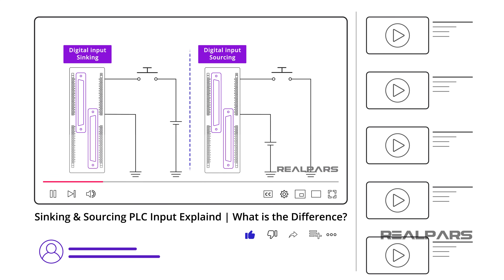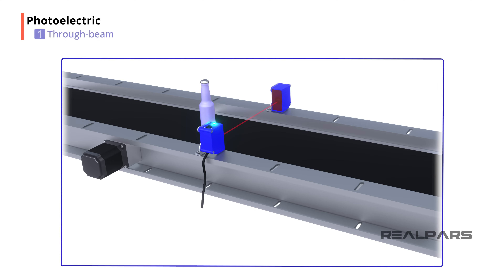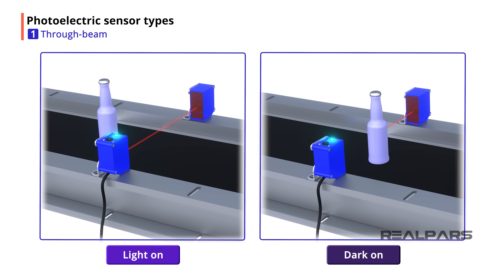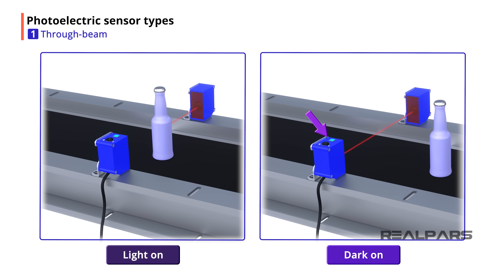If you would like more information on sinking, sourcing, PNP, and NPN, check out our video titled PLC Inputs Sinking and Sourcing. There is a link for this video in the description. Some photoelectric sensors have a light on/dark on mode selector switch. With this switch, you can change when the sensor's output turns on and off. In light on mode, the sensor's output will be on when the light can reach the receiver, and off when the light is blocked. In dark on mode, the sensor's output will be on when the light is being blocked and not reaching the receiver, and off when the light is reaching the receiver.